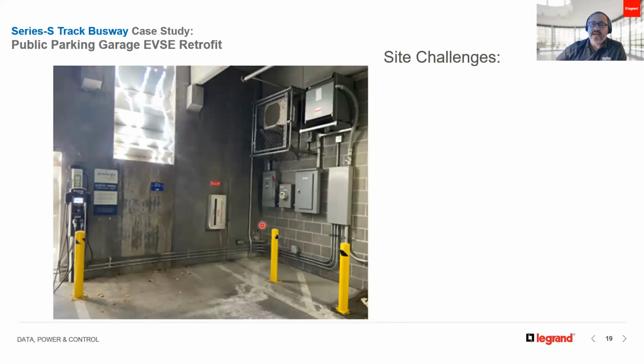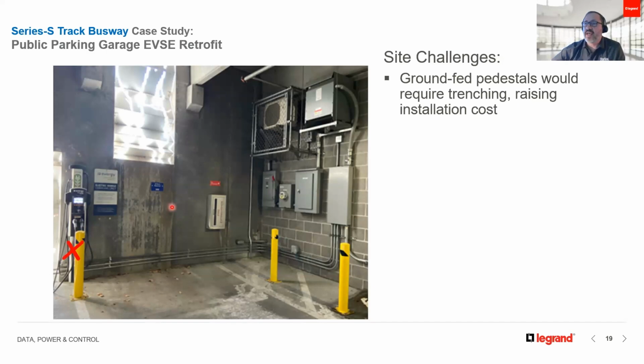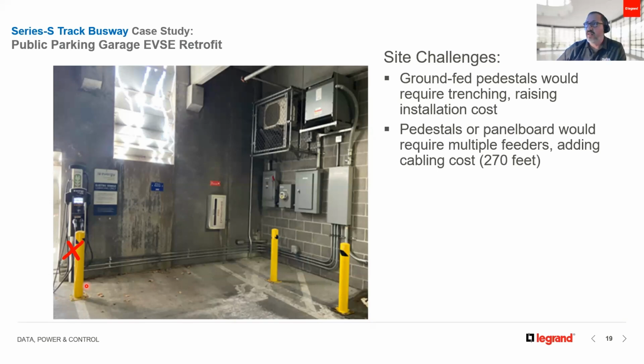So this building already had 3 wall mount pedestals. You can see one of them right here. But here's the issue: if they would have utilized a typical EV pedestal, they would have had to shut down more of the area. And by the way, the first 2 chargers I showed in the previous pictures are located right at one of the main entrances to the parking garage, so traffic was also an issue. And every time you trench, you have to put concrete and wait for it to dry, which adds time and money.